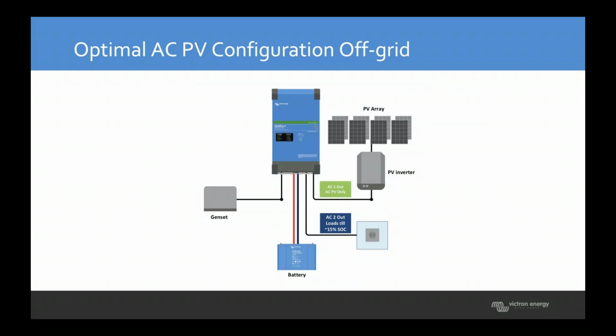But in an off-grid system, you might wish to have it instead like this, where the loads are connected to AC out 2, and they get disconnected when the battery state of charge reaches, say, 15%, or the battery voltage reaches a low threshold point, but not shut down, and that only leaves the PV inverter connected on the AC1. When the PV inverter is the only thing connected on the AC1, then it'll still stay online, and then the next morning when the sun comes out, it'll generate power, which will charge the battery up, and that'll then close that relay and reconnect the loads on AC2.